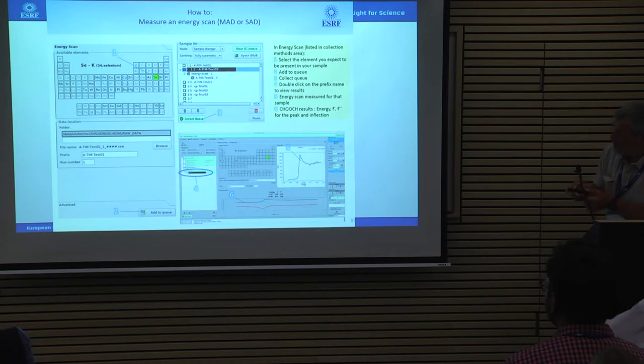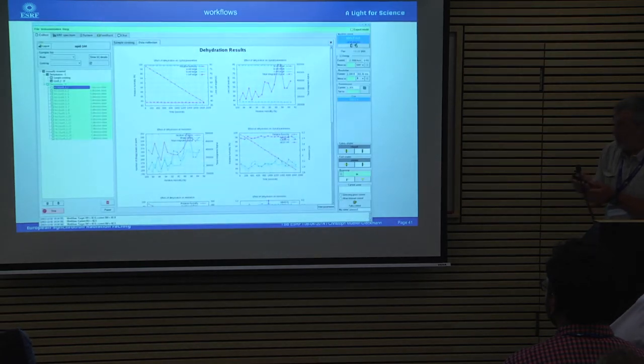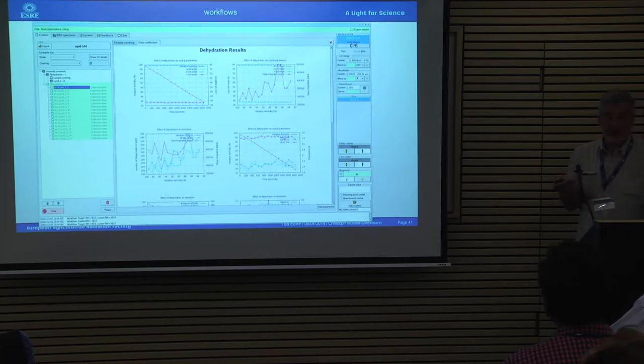Additionally, most of our beamlines are equipped with a kappa goniometer, allowing us to change the orientation of the crystal. With very large cell parameters it's important to properly orient the crystal. We can do this reorientation using X-ray diffraction images or visually. Also, we can collect data at room temperature using a device called a humidifier, which controls humidity during data collection. There is a workflow where humidity is changed and the program automatically looks for improvement in diffraction — this works not very often, but if you have large cell parameters, it's worth trying.